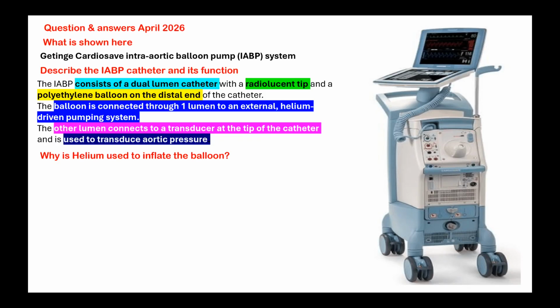Low density, sir. Low density. Non-reactive. It's an inert gas. Short diffusion. It causes a laminar flow. Low density will cause a nice laminar flow to expand and deflate without turbulence. Very good. Then any other reason? Supposing the balloon ruptures accidentally. It can be low solubility, sir. It can be absorbed. It will not produce any problem. What was the gas used when the machine was invented?